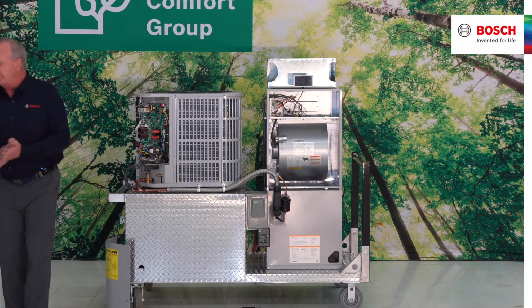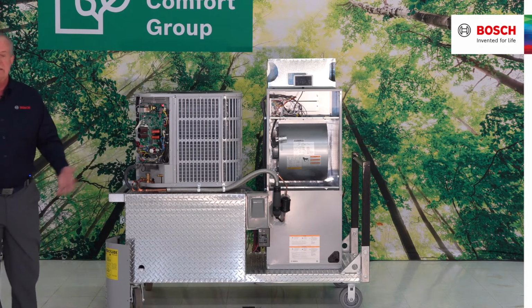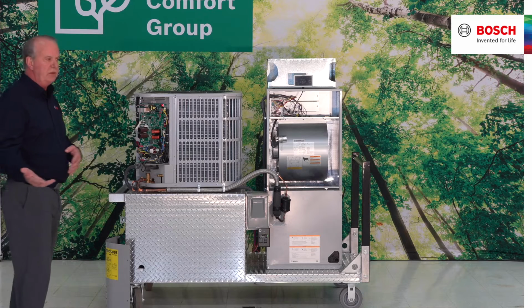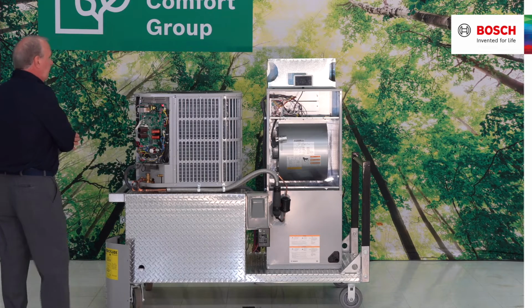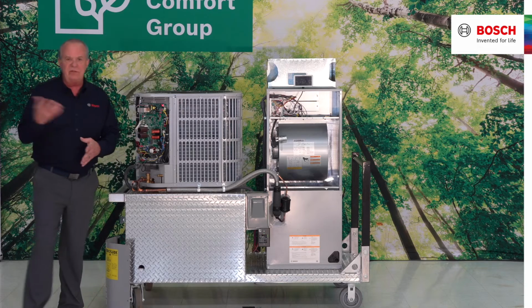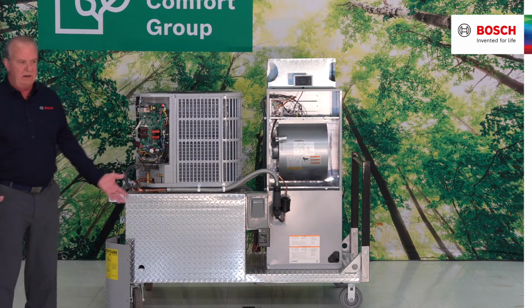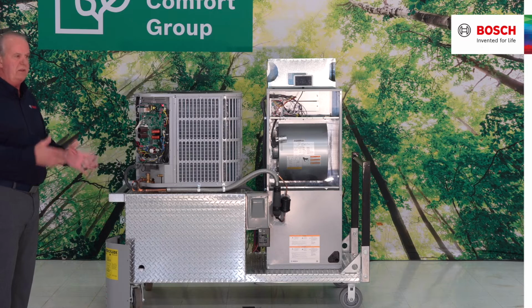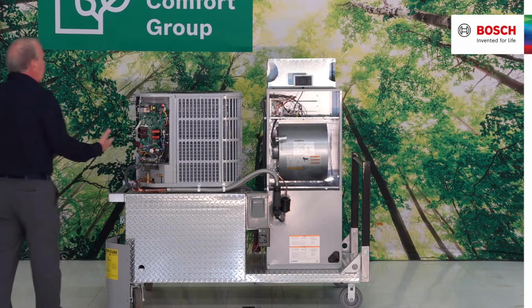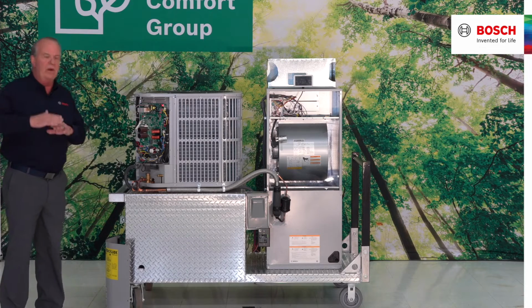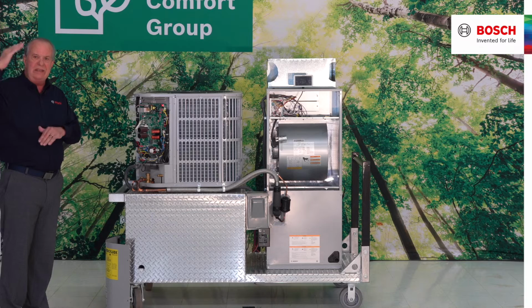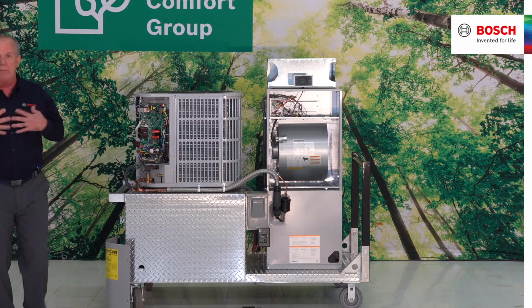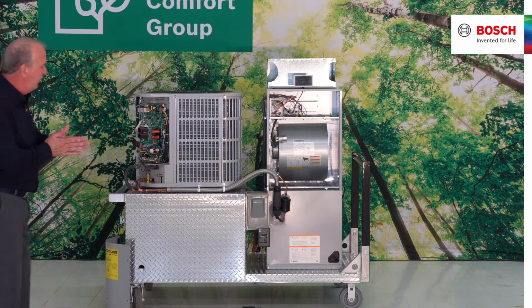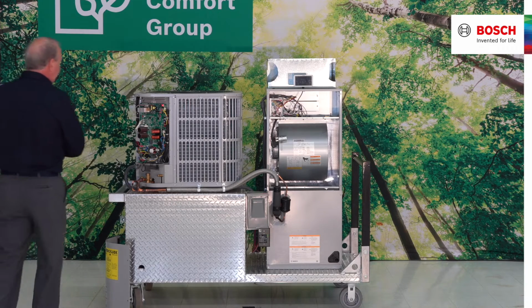Same with the 5-ton. The 5-ton goes from 15,000 to 66,000 BTUs. That gives us the capability to connect a 5-ton to a 3-ton if that was ever necessary, 3.5 or 4, and of course the 5-ton. So understanding that ramping or that variable BTUs or variable capacity was a critical component to me learning actually how this system functions and performs.